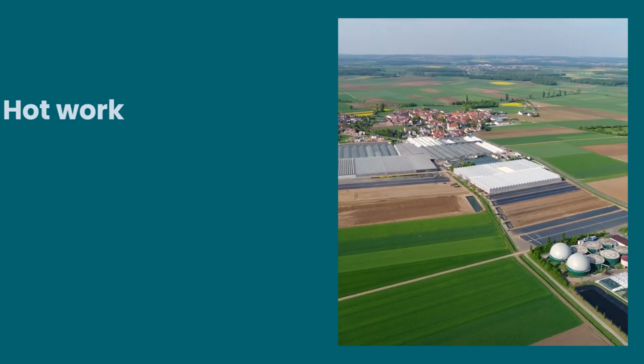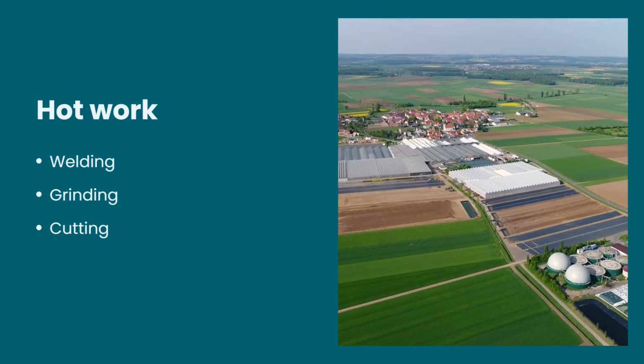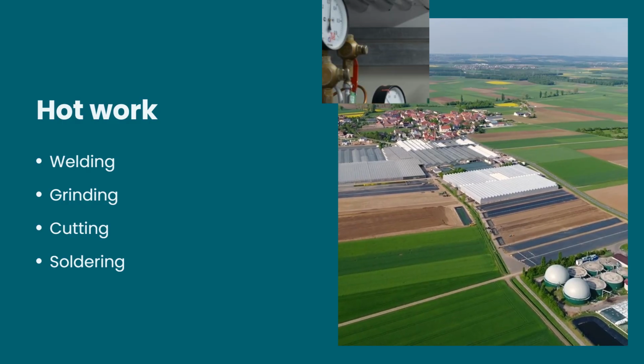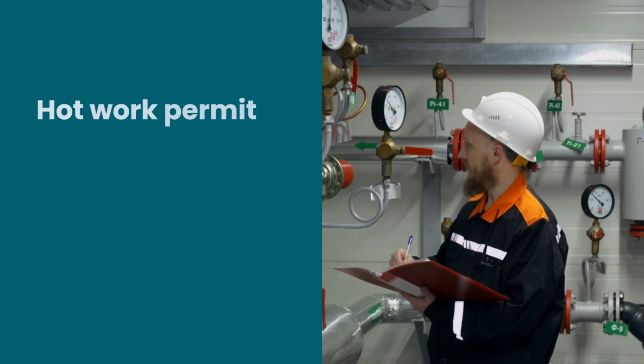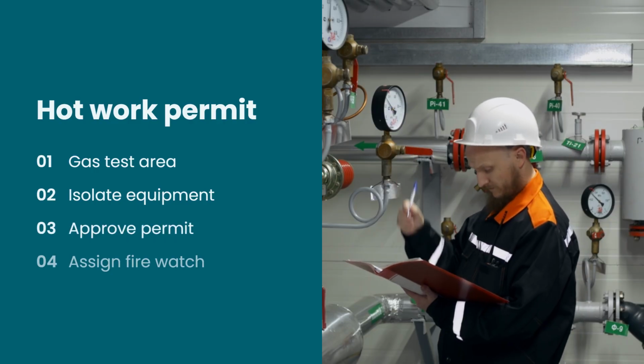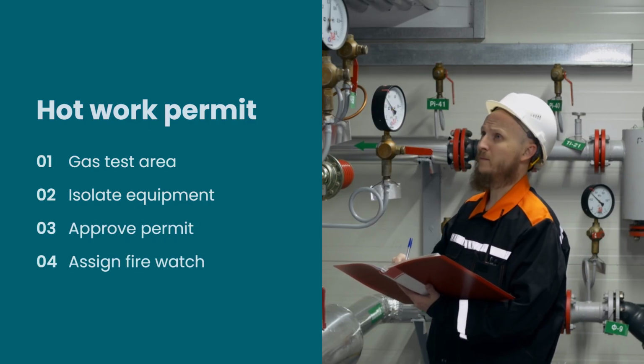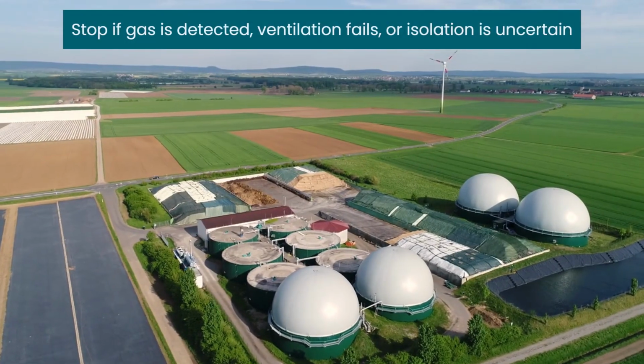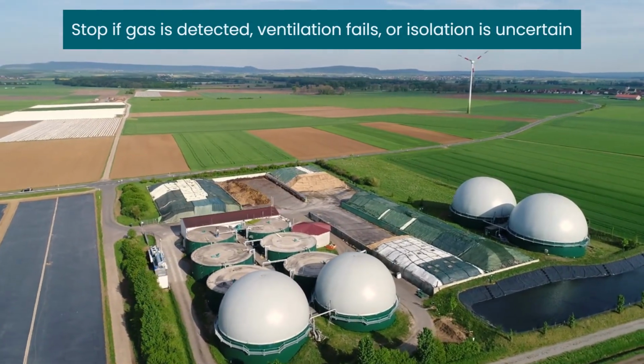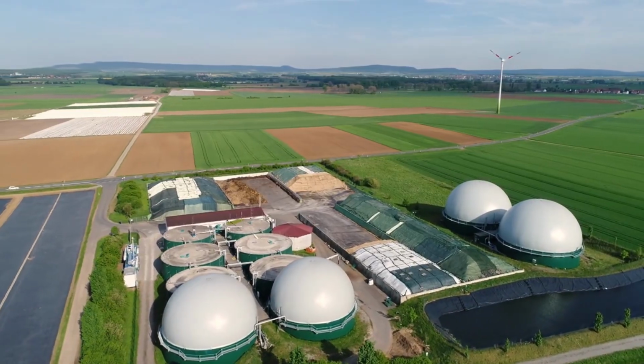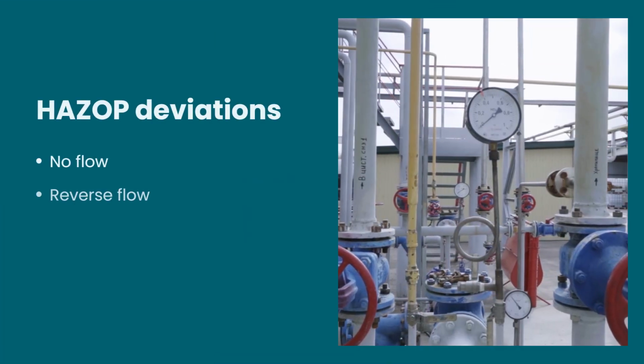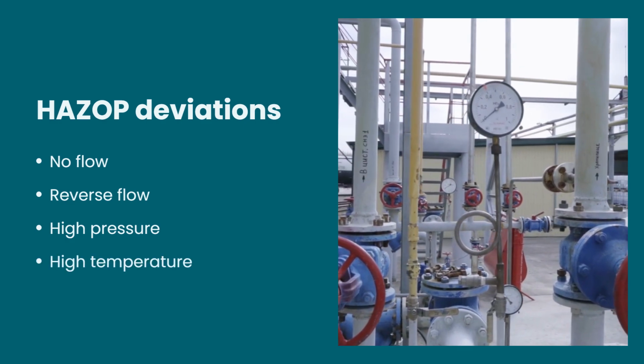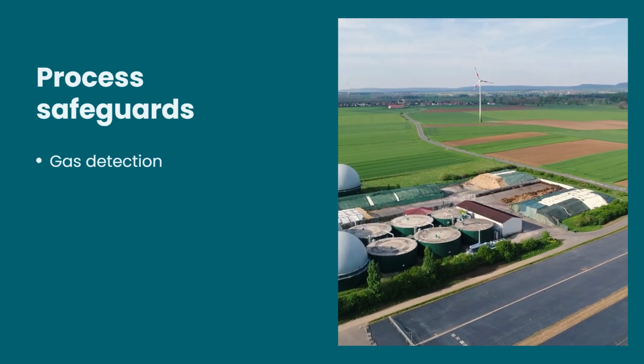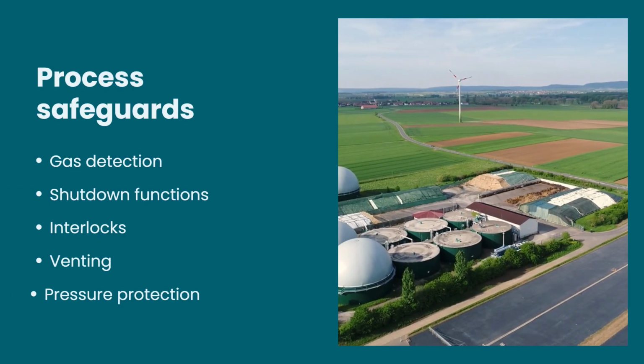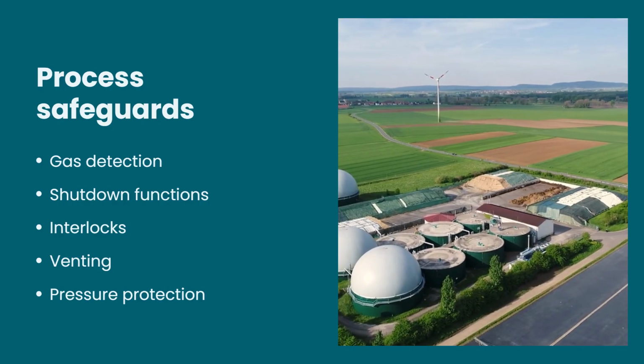Hot work includes welding, grinding, cutting, and soldering on or near biogas equipment. Before hot work, gas test the area, isolate equipment, approve the permit, and assign a fire watch. Stop if gas is detected, ventilation fails, isolation is uncertain, or the task changes. HAZOP studies examine deviations such as no flow, reverse flow, high pressure, and high temperature. The resulting safeguards may include gas detection, shutdown functions, interlocks, venting, and pressure protection.